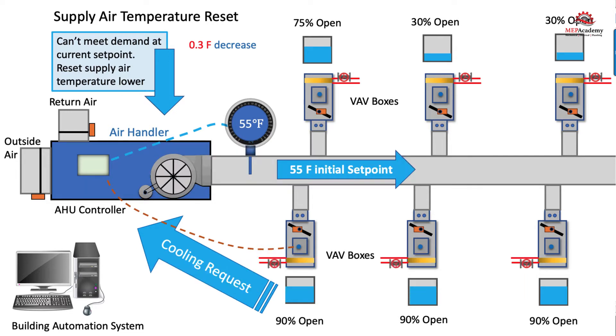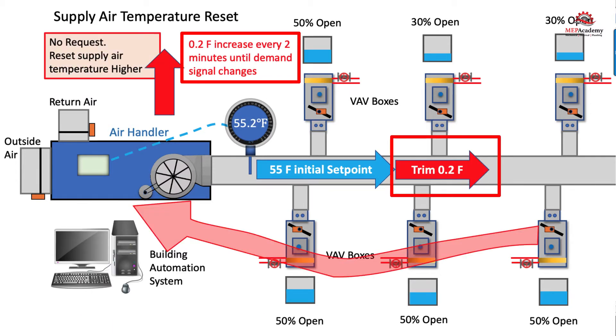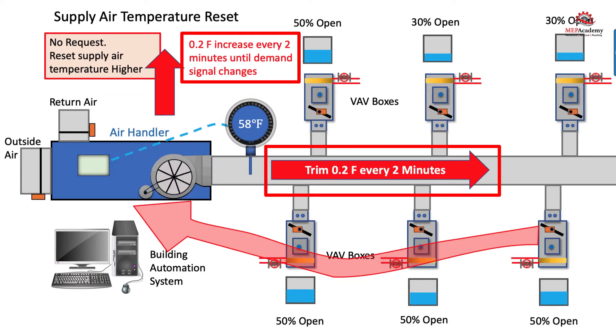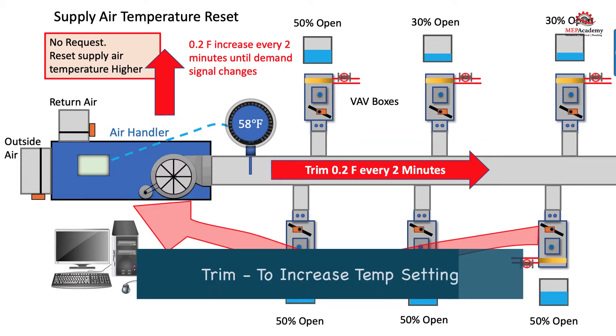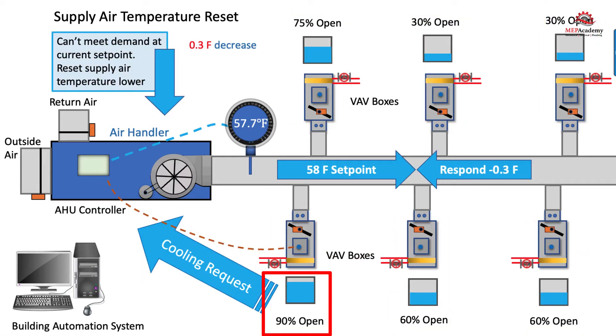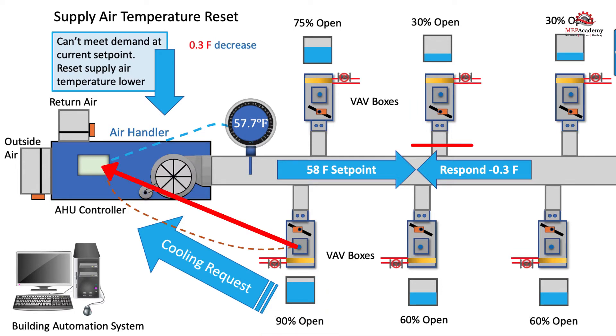For example, if no request is made, the supply air temperature is reset 0.2 degrees Fahrenheit, which would move the setpoint to 55.2 degrees. Every two minutes, or whatever duration is set by the controls programmer, the trimming of the supply air temperature will occur until a request is made from a zone. The VAV zone boxes can be programmed to make a request when any VAV box damper reaches 90% open. When the request is sent, the supply air temperature will respond by decreasing by a certain value chosen by the programmer.